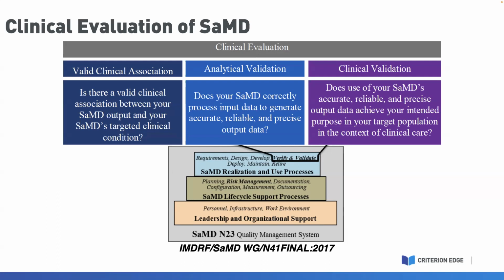You also want to show that the software meets its specifications and that those specifications conform to the user needs and the intended use. And the analytical validation is going to be generated and determined by the manufacturer during your verification and validation phase of the software development lifecycle using your QMS. It's required and necessary for any software as a medical device.